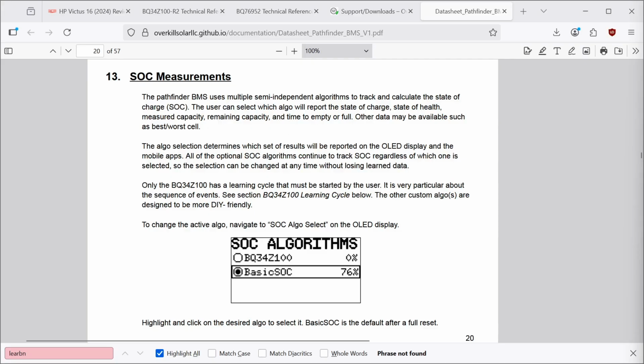The Pathfinder BMS uses multiple semi-independent algorithms to track and calculate the state of charge. On this menu, you can see the new algorithm I added is called Basic SOC, and it's selected by default. You can also go back and select the Z100 — changing this selection just changes the data source, so it changes what data you see. The underlying calculation keeps running for both, regardless of which one you select.